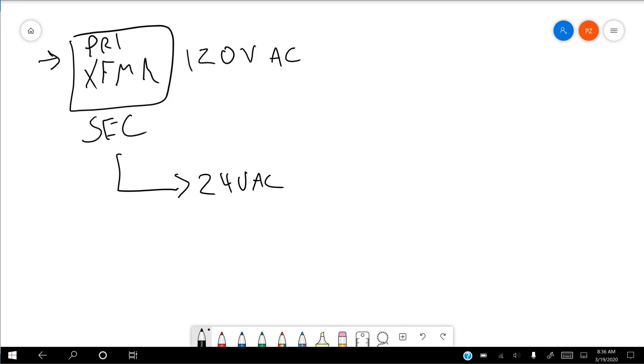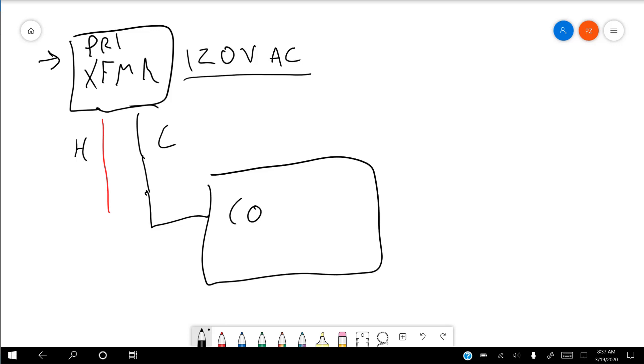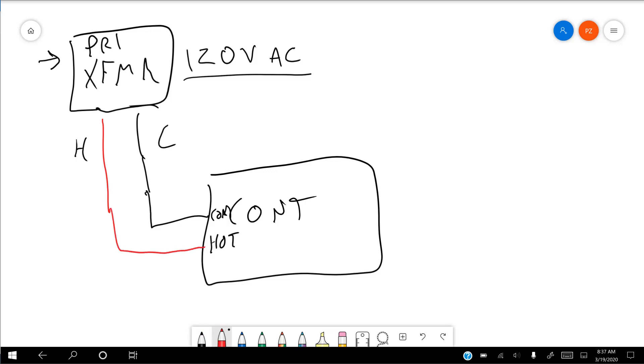So we've got our primary getting 120 volts AC coming in, and 24 volts AC coming out. Typically what's coming out is going to be a hot and a common. I'll use red for the hot and black for the common. These are going to go to our controller, which has a common and a hot. The hot is where power starts coming in, and the common is where it returns to the transformer.